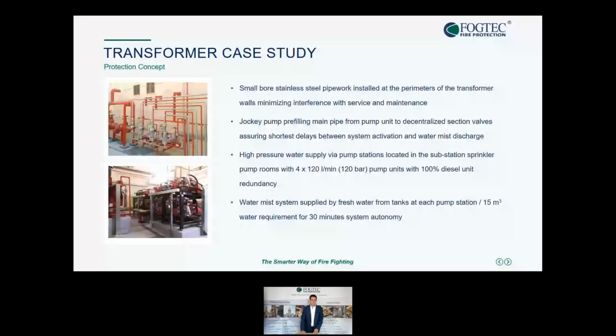We did an independency of 30 minutes, generated by 15 cubic meters of water. This was one of the big topics that drove the decision to go with high pressure water mist, to reduce the water amount used. The storage of water and the treatment of used water after a fire incident is always a big topic for a customer and a big argument to reduce the amount as much as possible.